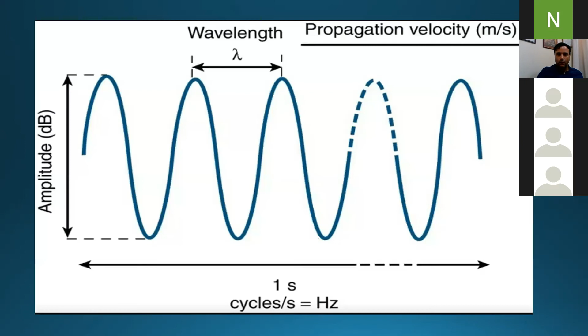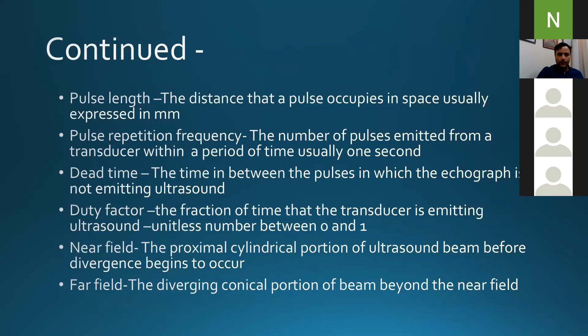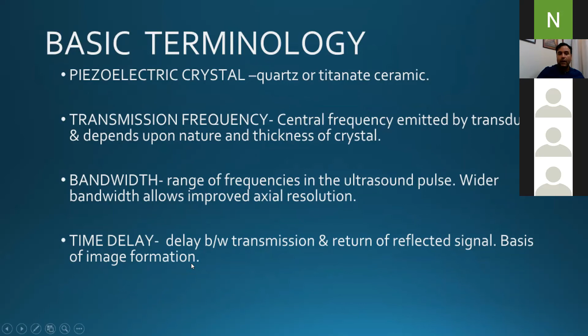Now, the piezoelectric crystal, what I was talking about, is made of quartz or titanate ceramic, right? So the piezoelectric crystal, when placed in an electromagnetic field, generates a signal, right? So what exactly happens? I actually want to show you. Transmission frequency is the central frequency emitted by the transducer, right? Then the bandwidth is the range of frequency of the ultrasound pulse. A wider bandwidth allows improved axial resolution. And then there is the time delay between transmission and return of the signal.